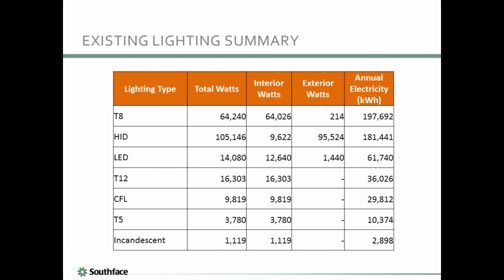This is a summary of all of the lighting that was surveyed in the recreation center assessments. The vast majority of the lighting is T8. It consumed the largest amount of the annual electricity. The next highest consumer of electricity was HID, so metal halide and sodium vapor fixtures. The majority of these fixtures are located outside. So there were some metal halide fixtures located indoors.